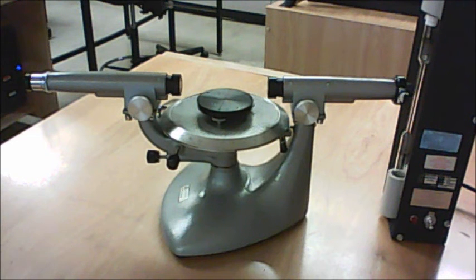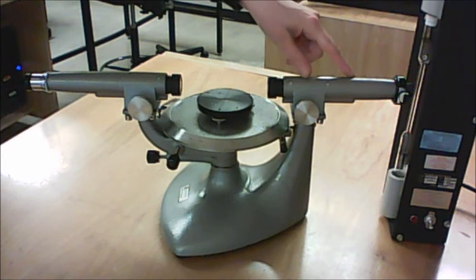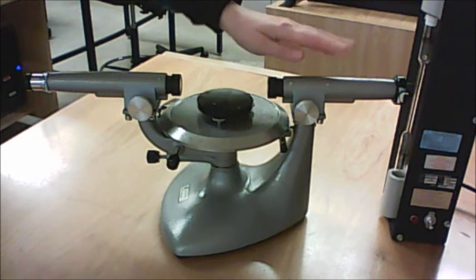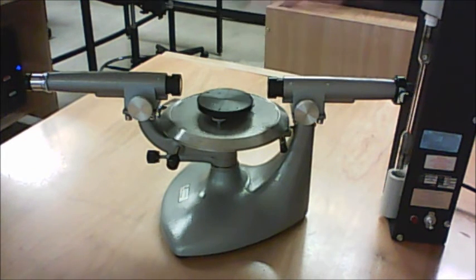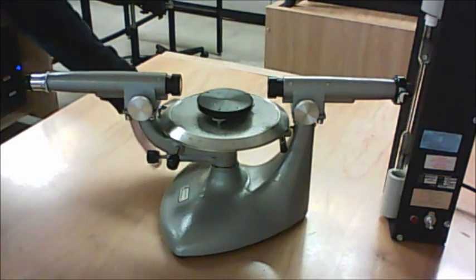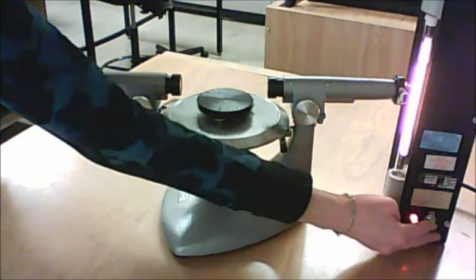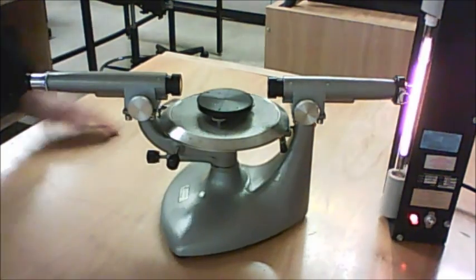The last thing you want to focus is your collimator. So it's got a focusing knob as well. But in order to focus it, you need your light source. So take your spectrometer back to the lab, get it all set up, turn on your light source.